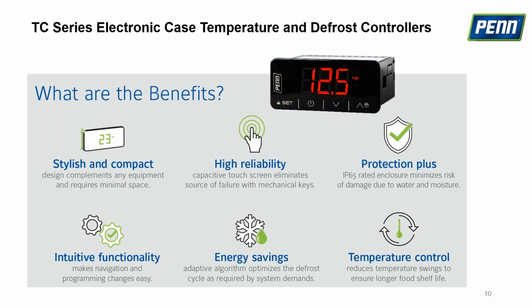The big one everyone likes to talk about is energy savings. We have adaptive defrost, though you can also use your own scheduled defrost. With our adaptive algorithm, when you start using the TC, there's a calibration phase where the controller learns how your display case or walk-in cooler is working. Then it starts its working phase, starting the defrost cycle whenever needed, as efficiently as possible. After every cycle it gets smarter, not just more efficient but more accurate.